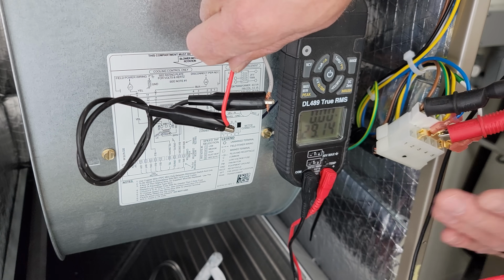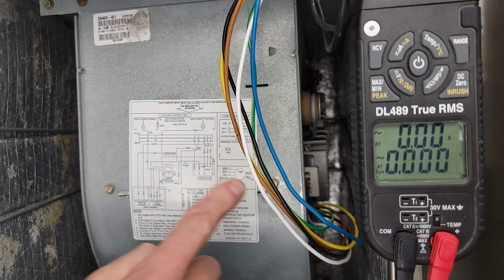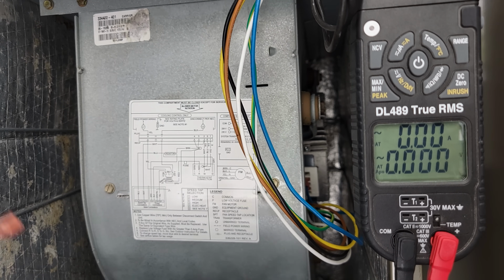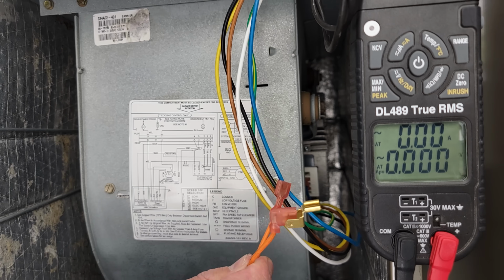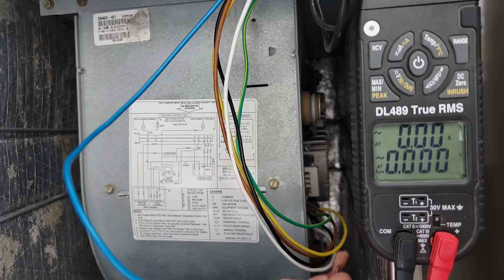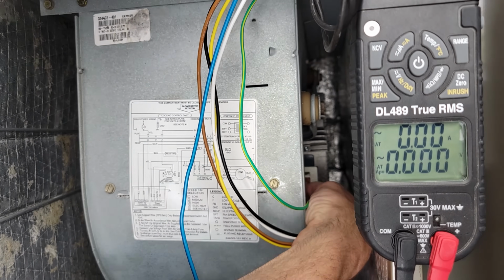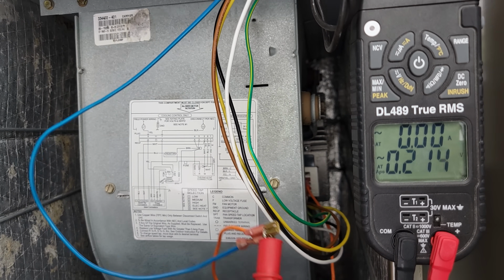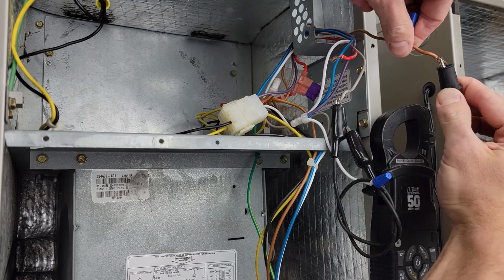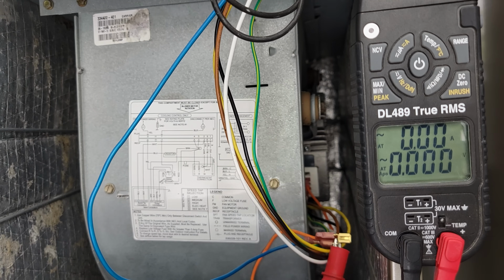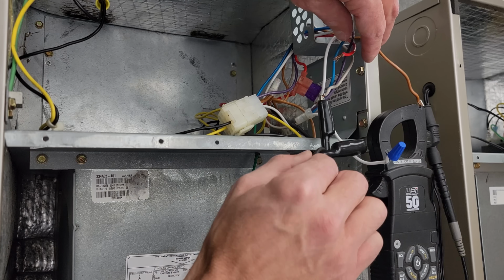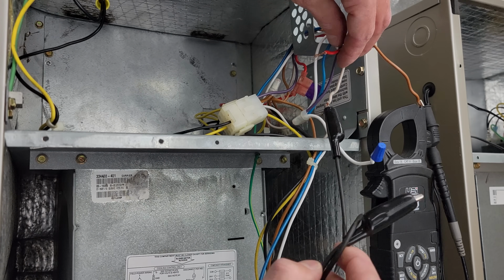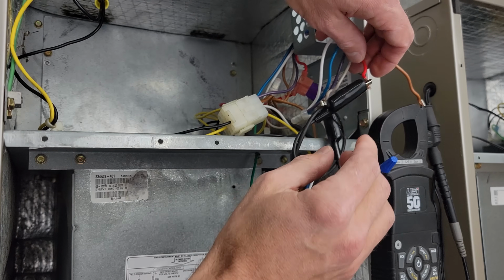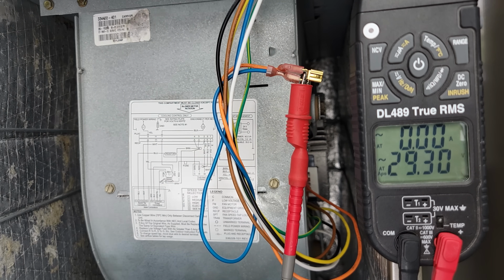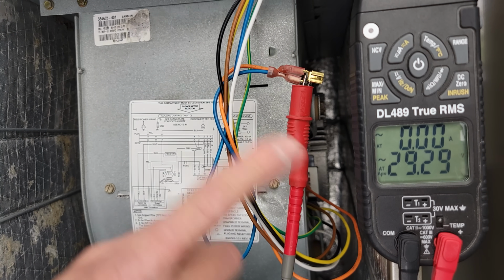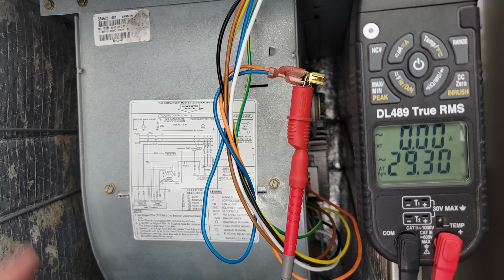Now this one's a Broad Ocean motor, and now I want to jump over to an X13 blower motor. Here we have an example of an X13 blower motor back here. We're not going to pull it out. We're only going to take this one speed wire out, and we're going to put this little adapter on. So we got our one clamp here, and we're going to put our other clamp on the common. Now we've turned our power back on, and we're going to put a call for the fan to turn on, and you can see we have a jumper wire on this gray wire, and so we can just jump right over to our R, and as you can see right down here, gray means fan. So you see we're measuring 29 volts, and the blower motor is running, so we know that the blower motor is fine.